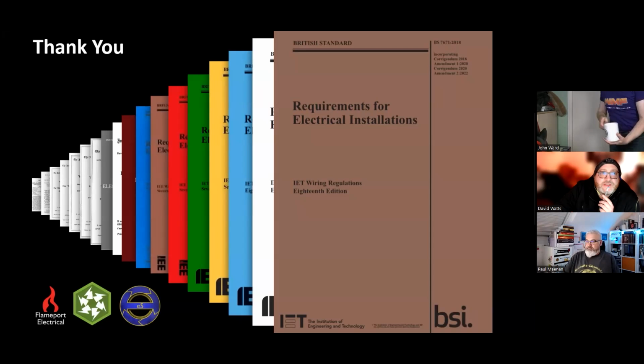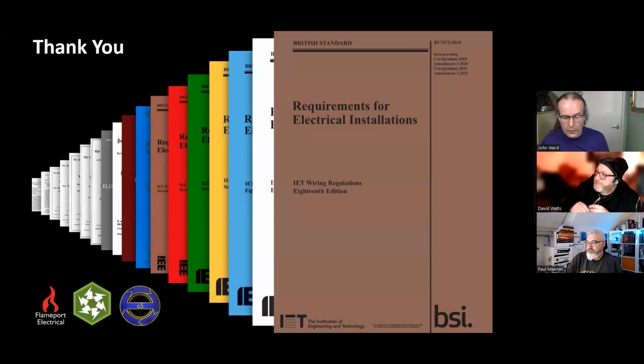All right. So Dominic says, on earthing on a TN system, we were putting the electrode in. This is where we talked about the picture of the conductor and the additional electrode at the intake. How is that practical with services in the ground and getting them 5 to 10 meters away? So it's obviously thinking about the electrodes and other services in the ground. How is it practicable?